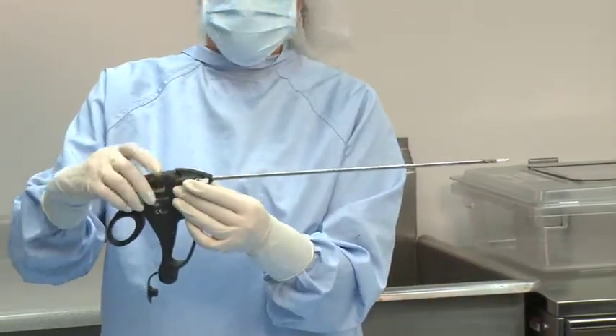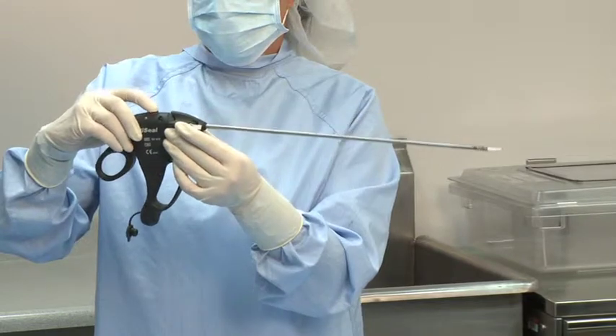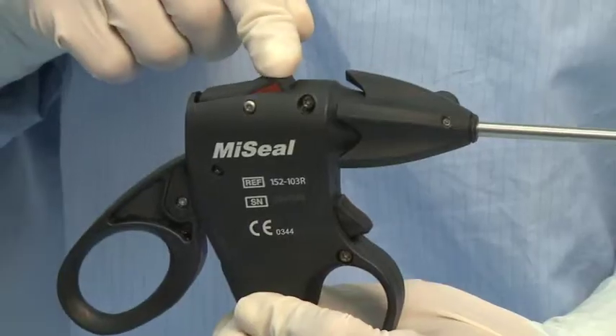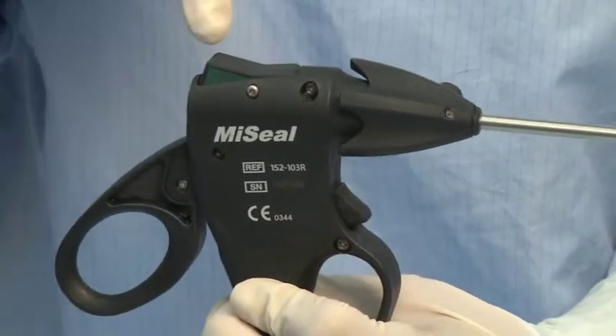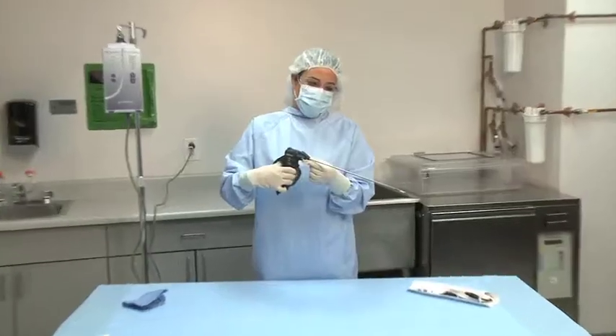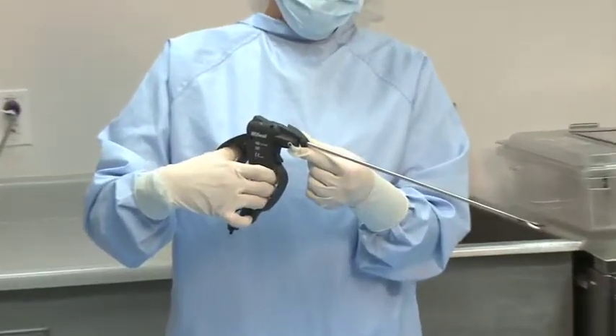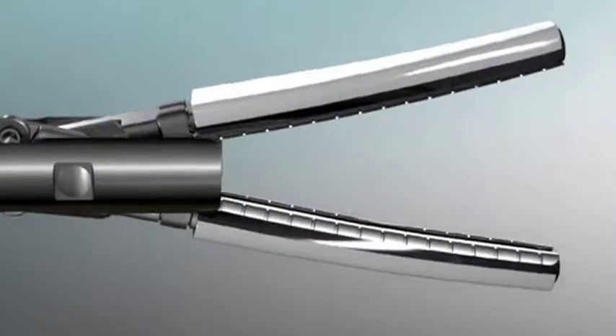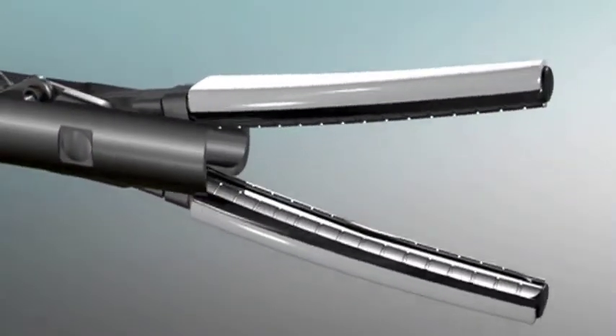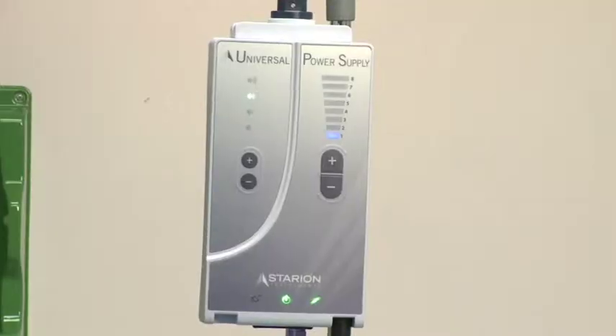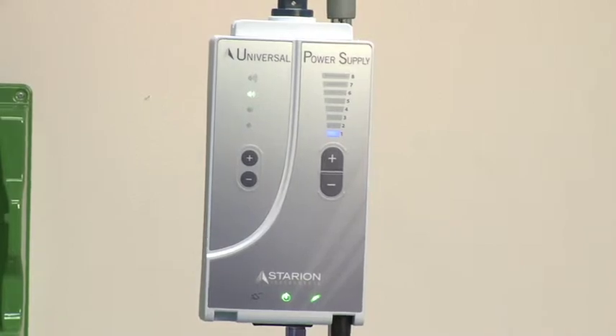Push the rocker button on the handpiece forward to the run position to disengage the shaft locking mechanism. A green graphic indicator will be visible on the side of the rocker button. Test the device by moving the thumb trigger to verify proper jaw movement. The device is now ready to connect to the Universal Power Supply, or UPS.